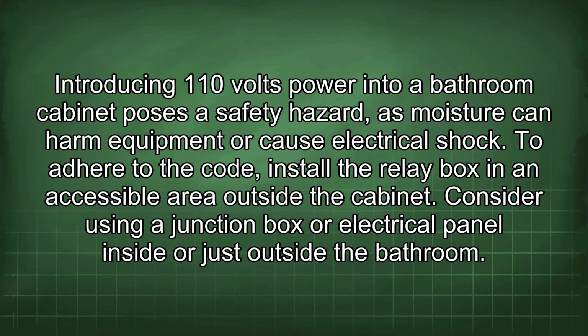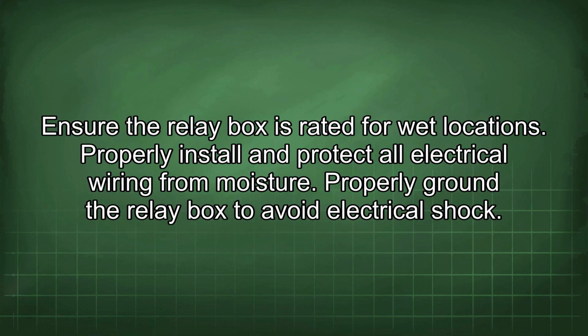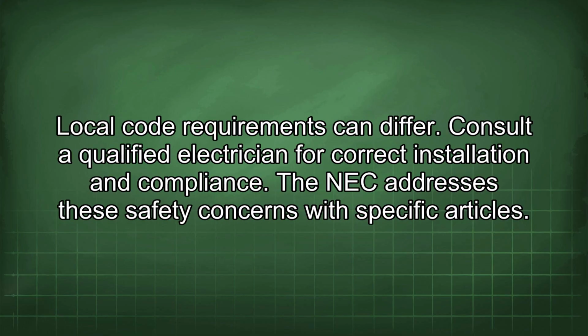Consider using a junction box or electrical panel inside or just outside the bathroom. Ensure the relay box is rated for wet locations. Properly install and protect all electrical wiring from moisture. Properly ground the relay box to avoid electrical shock. Local code requirements can differ. Consult a qualified electrician for correct installation and compliance.